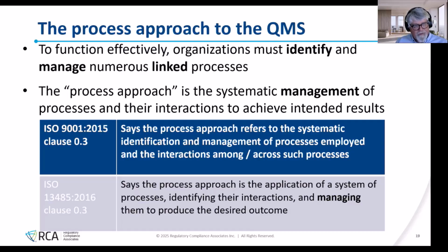So here are some definitions. This is from 9001-2015, the general standard for quality management systems, and then ISO 13485 specifically for medical devices. This standard, 13485, says the process approach is the application of a system of processes. So there's more than one process. There's a system of processes, identifying their interactions and managing them to produce a desired outcome, and desired outcome again means design intent.